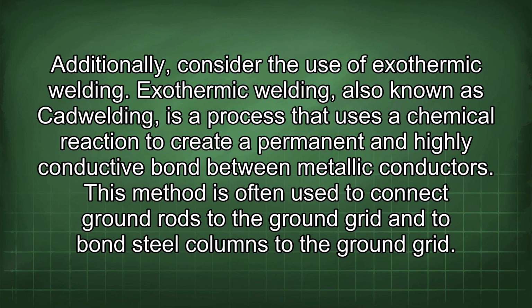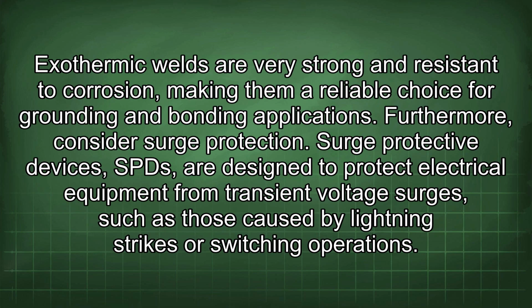Additionally, consider the use of exothermic welding. Exothermic welding, also known as Cadwelding, is a process that uses a chemical reaction to create a permanent and highly conductive bond between metallic conductors. This method is often used to connect ground rods to the ground grid and to bond steel columns to the ground grid. Exothermic welds are very strong and resistant to corrosion, making them a reliable choice for grounding and bonding applications.